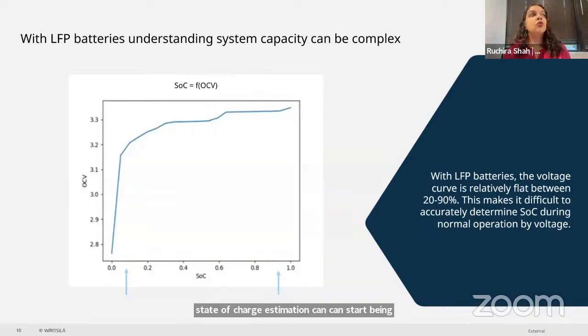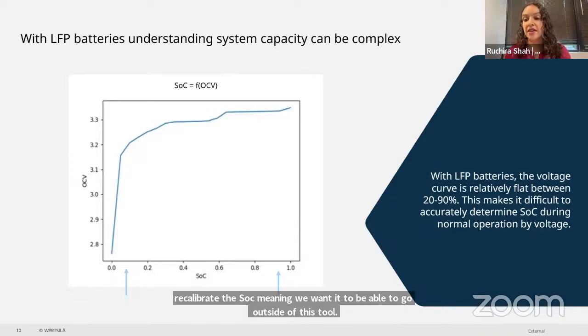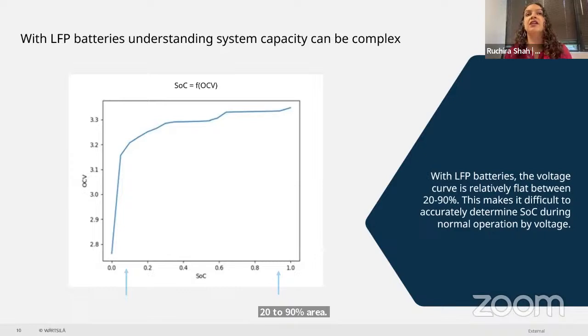When your state of charge estimate is incorrect, then your estimate of energy available to bid becomes incorrect. So we want to continuously allow our battery system to recalibrate the SOC, meaning we want it to go outside this 20 to 90% area so the battery management system can provide a more accurate estimate of the state of charge.